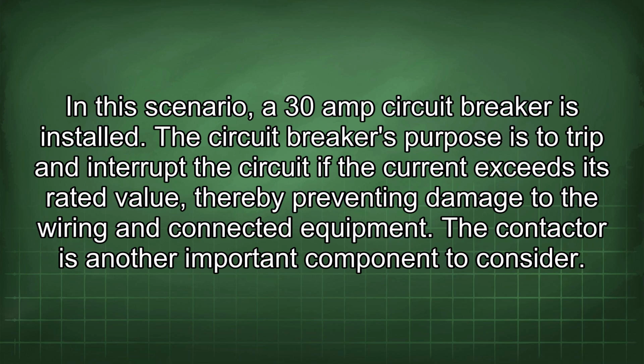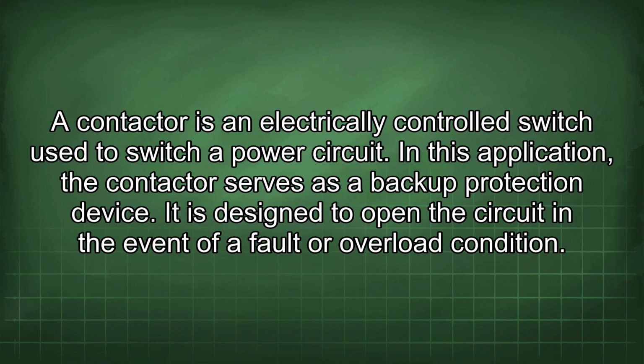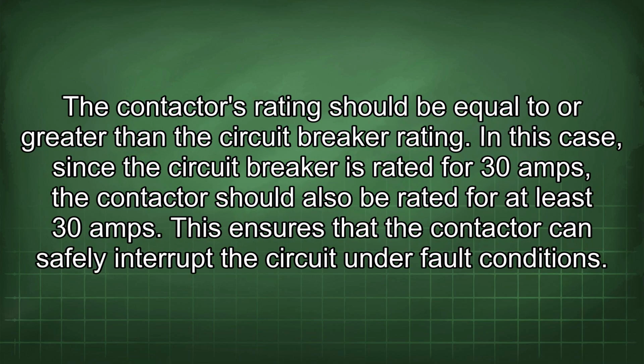The contactor is another important component to consider. A contactor is an electrically controlled switch used to switch a power circuit. In this application, the contactor serves as a backup protection device. It is designed to open the circuit in the event of a fault or overload condition. The contactor's rating should be equal to or greater than the circuit breaker rating. In this case, since the circuit breaker is rated for 30 amps, the contactor should also be rated for at least 30 amps. This ensures that the contactor can safely interrupt the circuit under fault conditions.